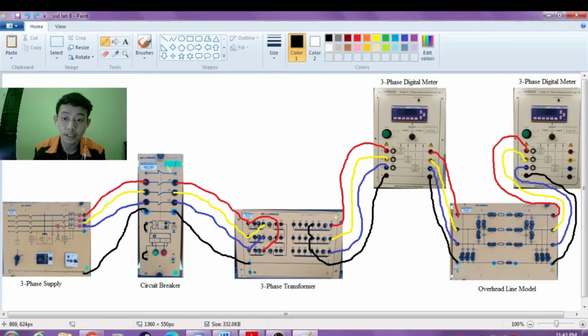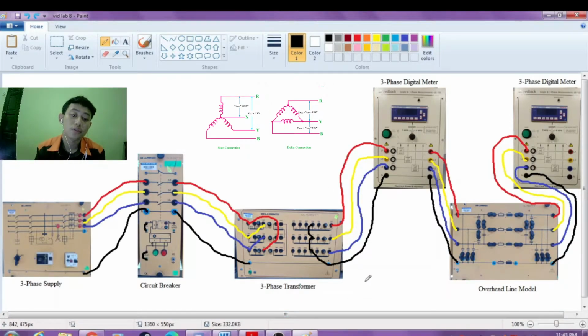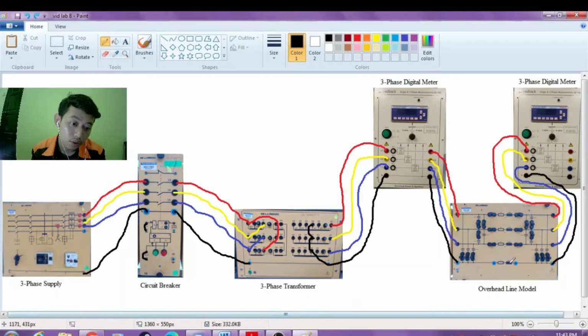I have completed all the connections, and this circuit is quite simple because all the connections are in series. Looking at the transformer, you will realize the primary side is in delta connection and the secondary side is in star connection. At the overhead line module, the bridging plug connects the capacitance to the line module. The function of the two digital meters, or measurement meters, is to get the value of the voltage for the outer conductor at the beginning and end of the line, and also to obtain the value for the active and reactive power consumed by one of the phases. So that's all for activity 1. Thank you.